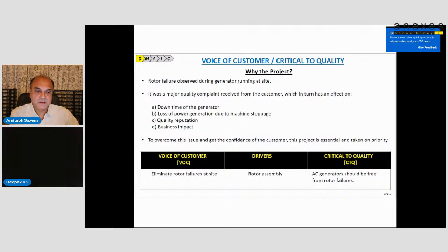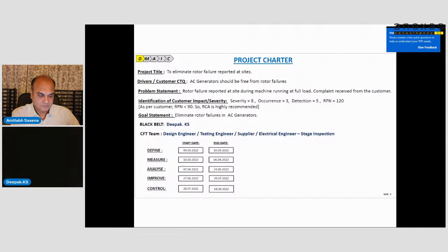You can see the voice of customer, the drivers with the rotor assembly, and critical to quality. The AC generator should be free from rotor failures. Next slide. This is the project charter. The project title: to eliminate rotor failure reported at sites. The problem statement: rotor failure reported at site during machine running at full load, that is up to 18 megawatt. The machine was running there, and there was a rotor failure. This was the complaint received from the customer. The severity is 8, considering the impact. The RPN, calculated from severity, occurrence and detection, is 120, but as per the customer the RPN should be less than 90. So the customer recommended a root cause analysis and actions.